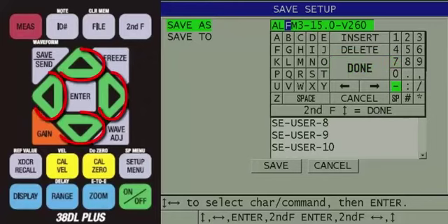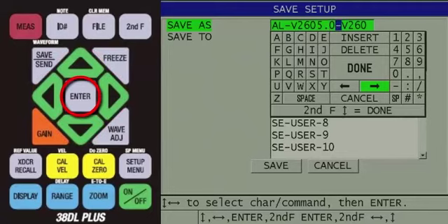Use the arrow keys to highlight a character, then press the Enter key to input the character into the Save As line. As you input characters, the existing setup name will start to be overwritten. Once you have finished entering the name of the custom transducer setup, use the arrow keys to highlight the right arrow, then keep pressing the Enter key until the last character on the Save As line is highlighted.